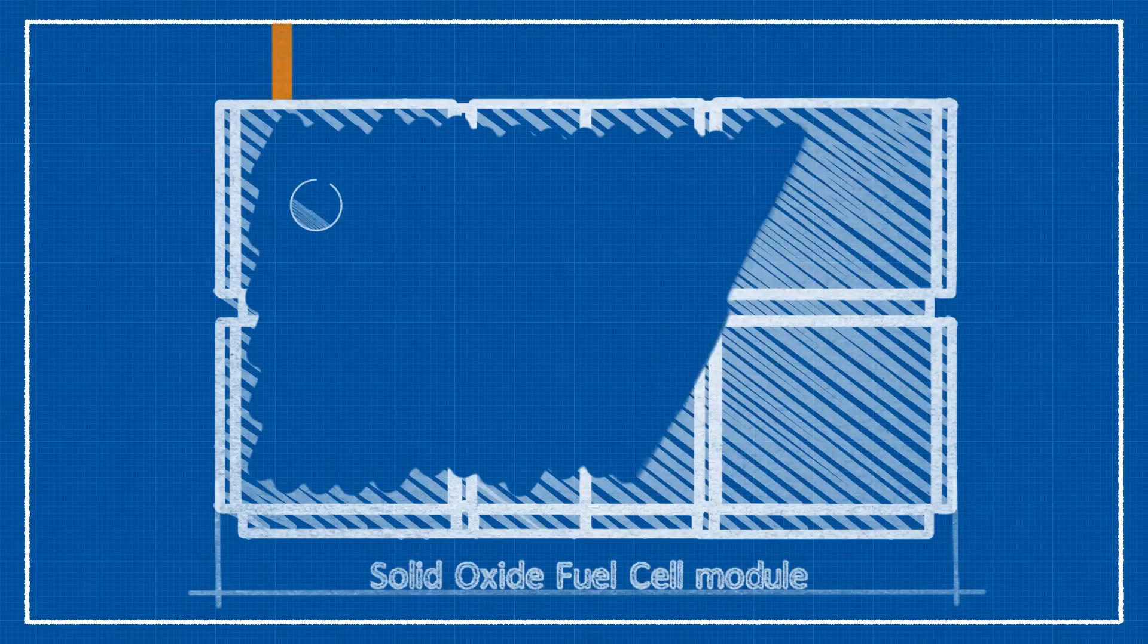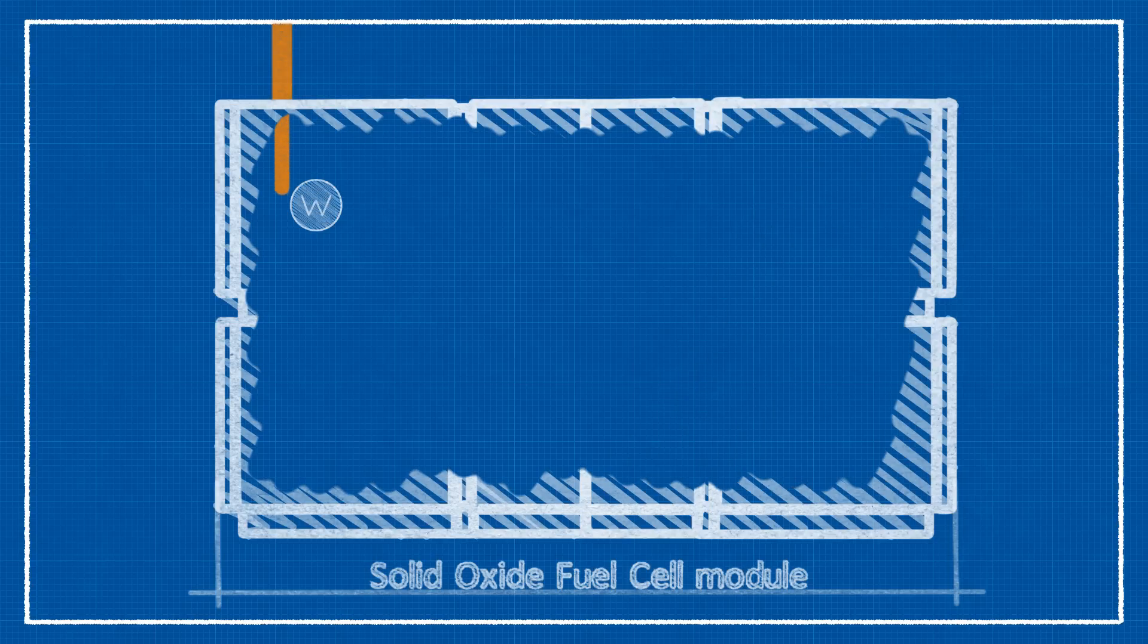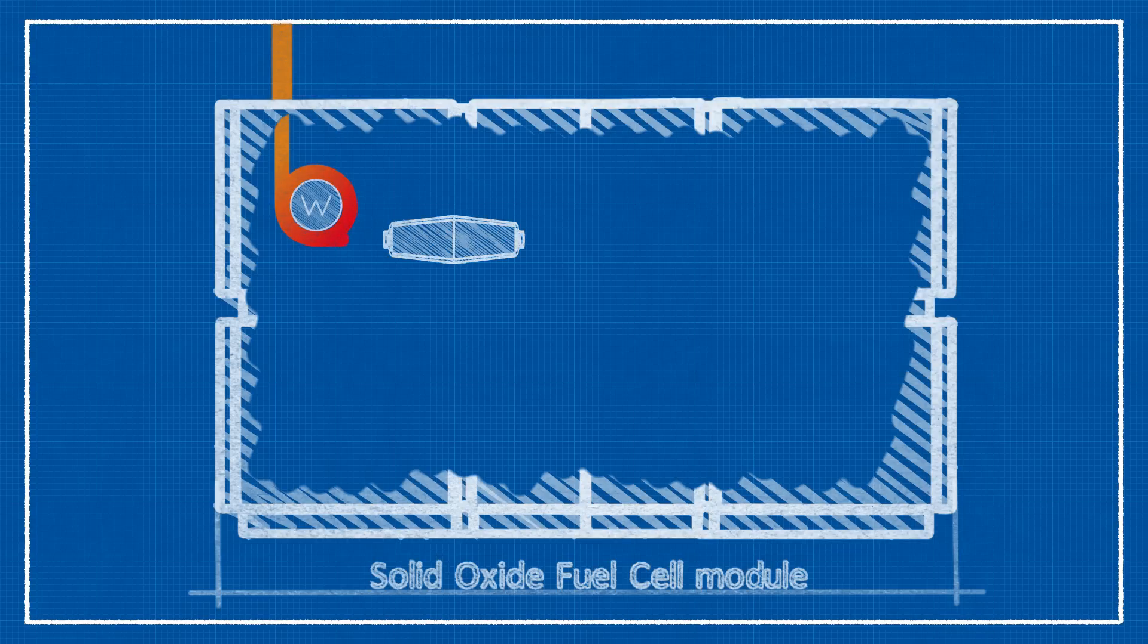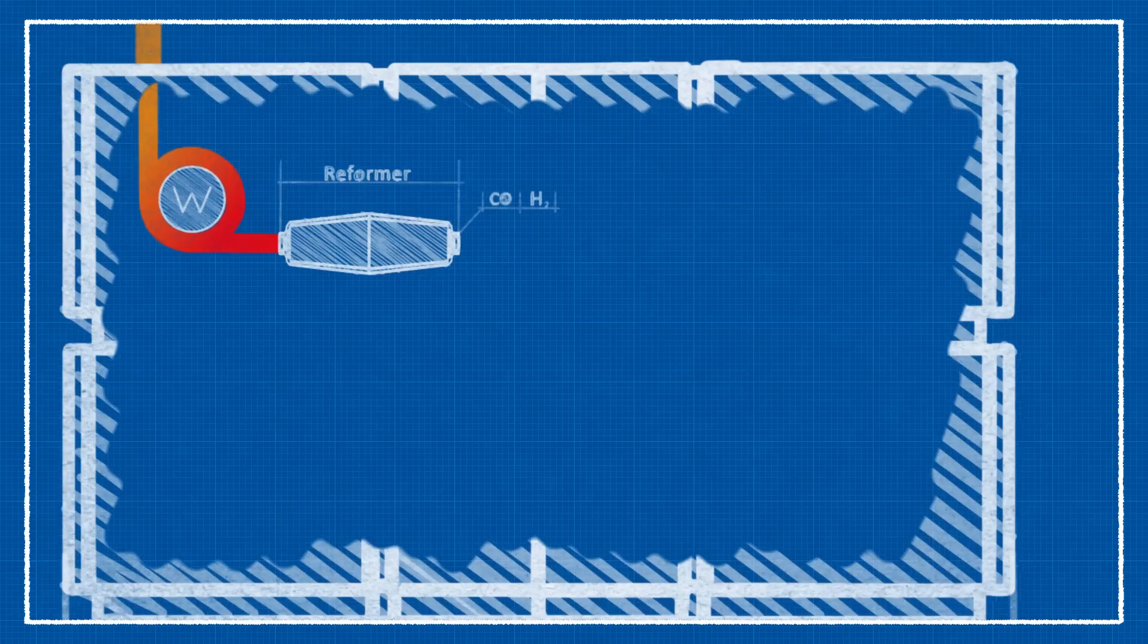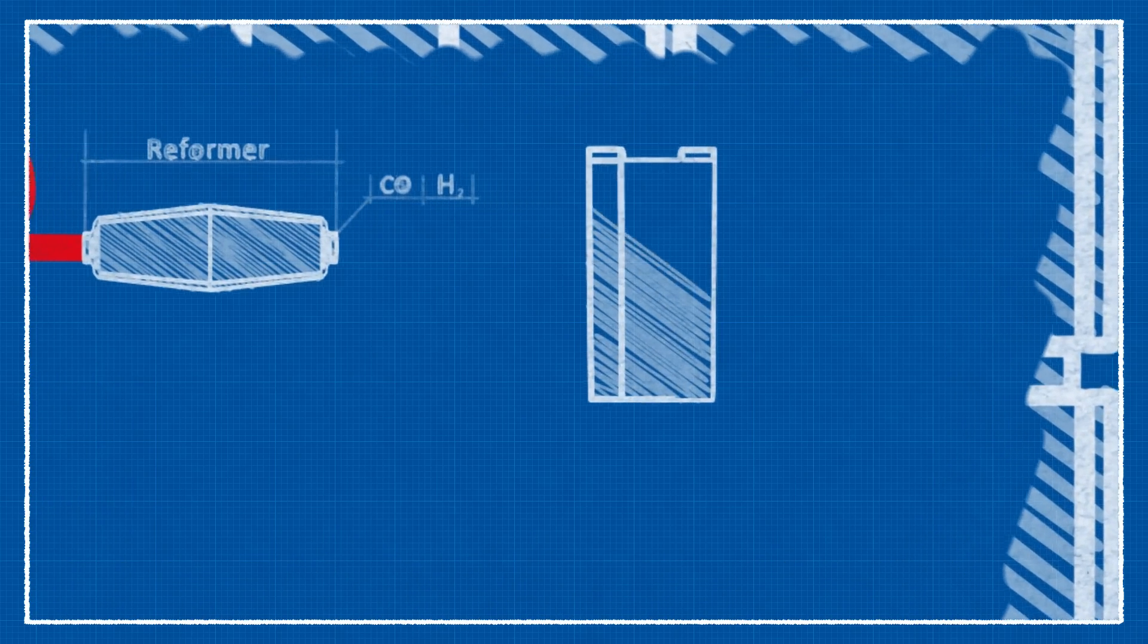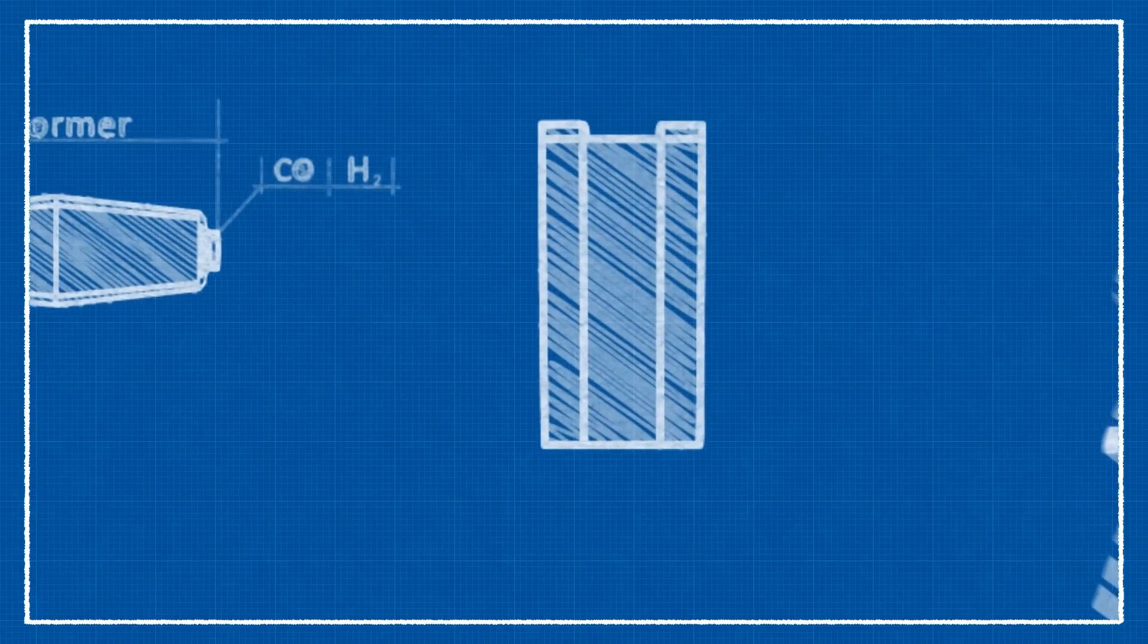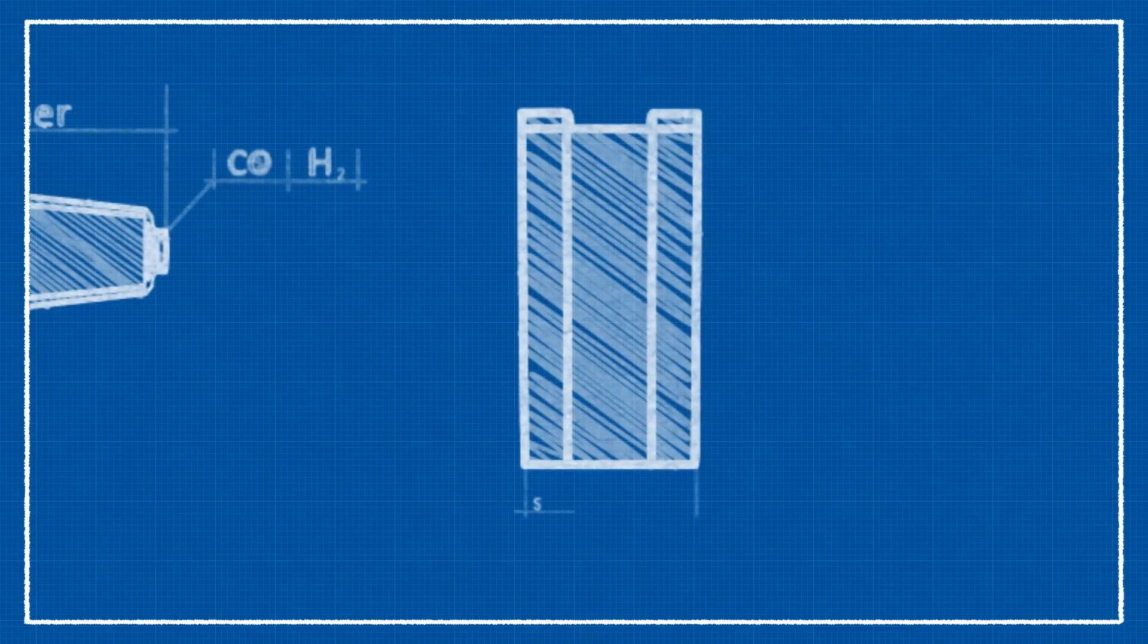In the SOFC module, biogas, made of methane and carbon dioxide, is first heated up. The reformer reactor then converts methane to hydrogen and carbon monoxide. The next step is the core of the DEMO SOFC project, a 174 kW SOFC.